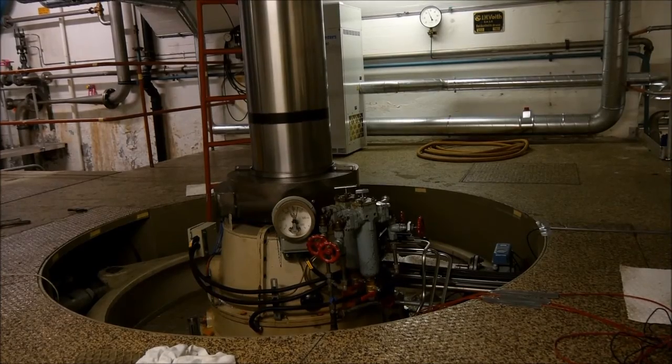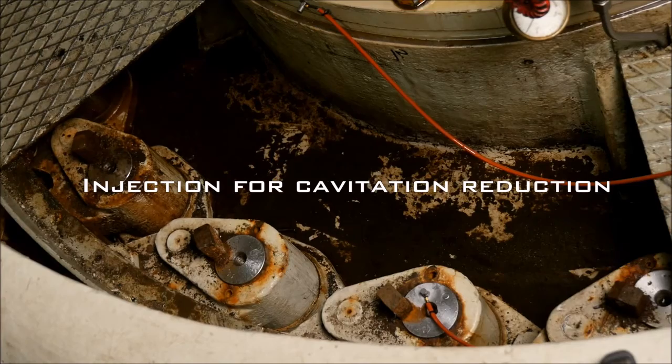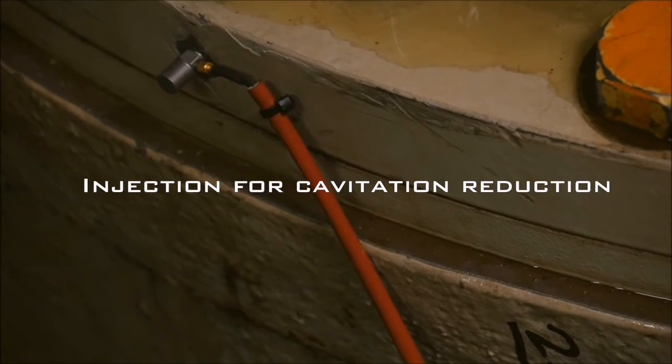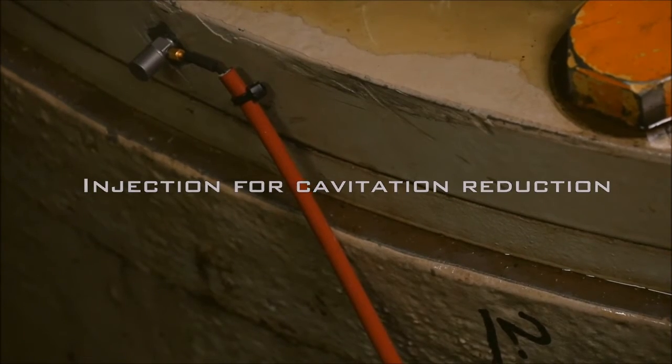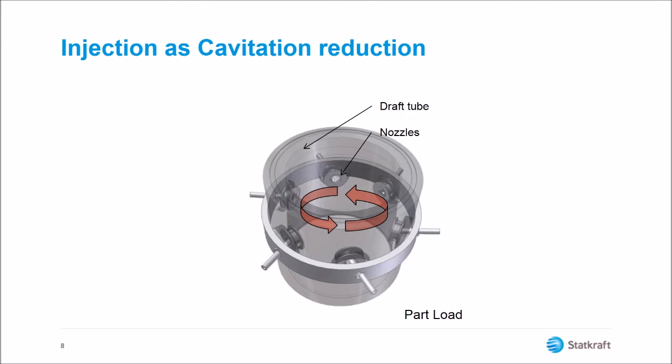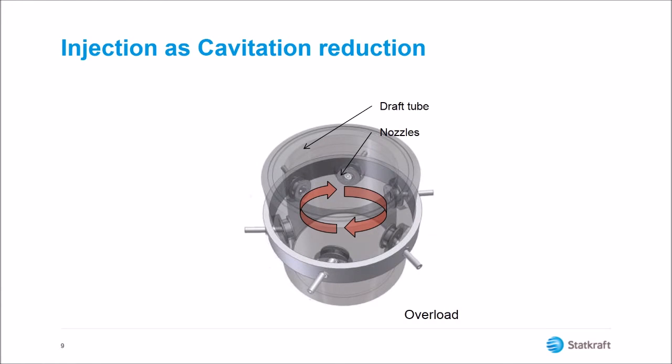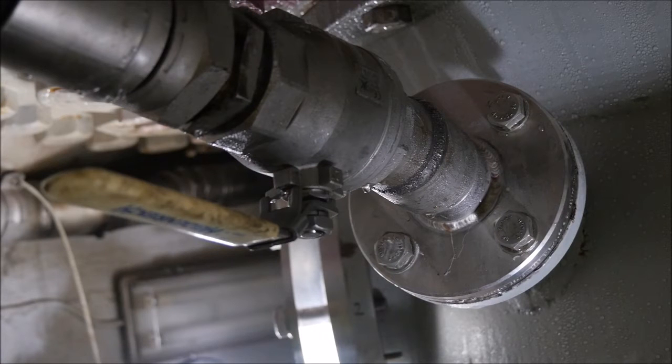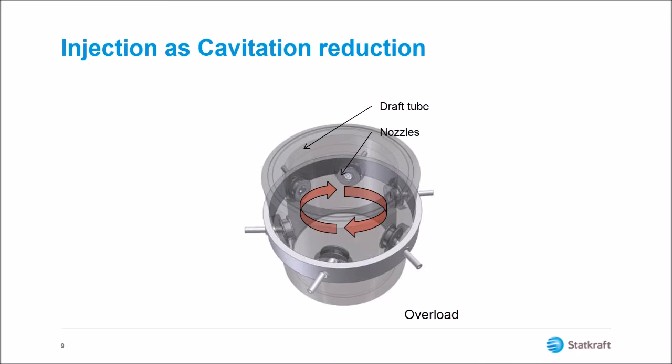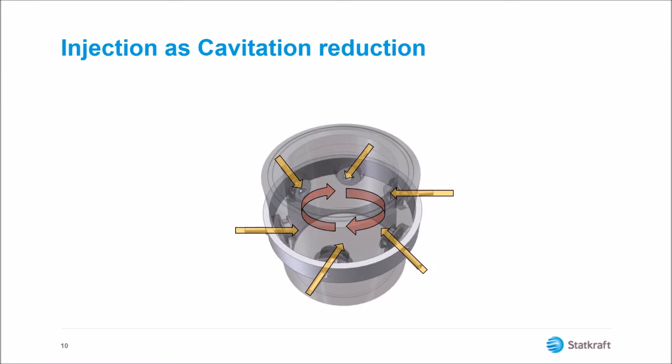The concept of water injection should in theory also apply to high loads, where cavitation often can occur. The spin in the water has at this point changed direction, so the nozzles would have to point in the opposite direction. But the effects should remain similar. Slowing the rotational speed of the water and thereby increasing the pressure in the draft tube should provide a countermeasure for cavitation on the runner blades.